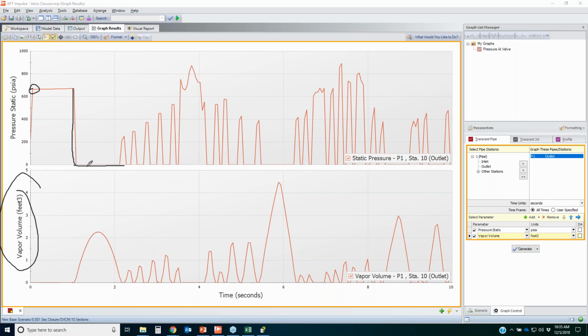When you drop down to vapor pressure during this time frame, you should see a vapor bubble form, and then once that vapor bubble collapses, you'll see an associated pressure spike. It drops to vapor pressure again, and then there's another vapor bubble. Once it collapses, you have another pressure spike. And then when it drops for a significant amount of time, you have a really large pressure spike there. And so that's the transient response that you can see.